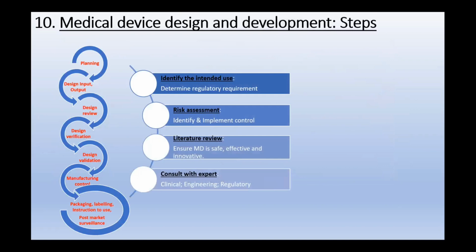The next slide is about the medical device design and development steps. These are the steps which have to be followed by the medical device manufacturer before undertaking any manufacturing process. Firstly, planning, then design input, output, design review, design verification, design validation, implementing manufacturing control, then packaging, labeling, and instructions for use provided on the packaging, and then comes post-marketing surveillance.